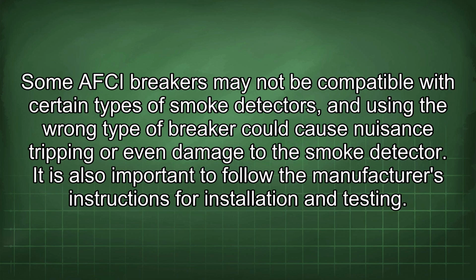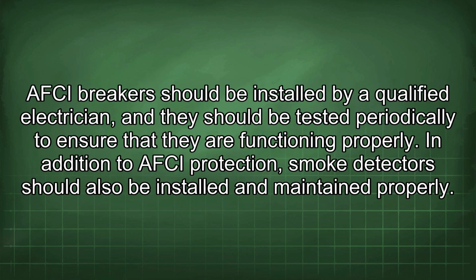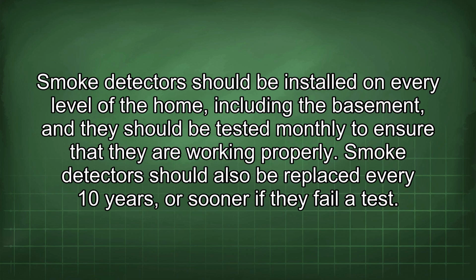It is also important to follow the manufacturer's instructions for installation and testing. AFCI breakers should be installed by a qualified electrician, and they should be tested periodically to ensure that they are functioning properly. In addition to AFCI protection, smoke detectors should also be installed and maintained properly. Smoke detectors should be installed on every level of the home, including the basement, and they should be tested monthly to ensure that they are working properly.